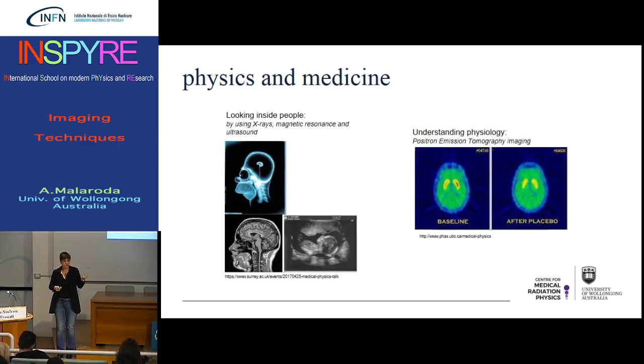How far the positron is going to travel before it's going to interact with an electron, that's an important information. It can be up to millimeters. So I'm going to get this position wrong if I don't correct for that. And what I can do is making an educated guess, knowing that in that material, the positron emitted by that radionuclide that has got that energy will travel more or less that distance, or in average, that distance before it interacts.